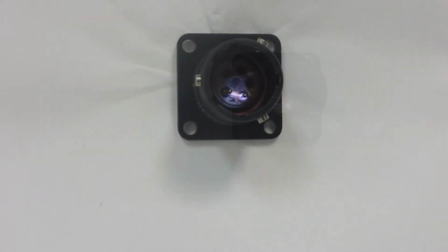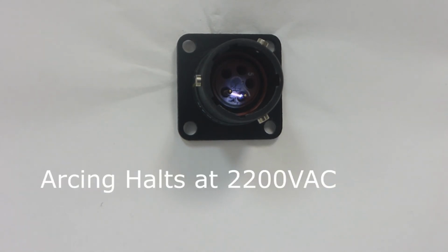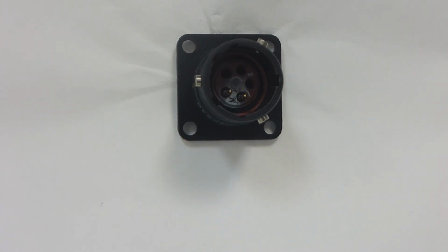Now we adjust the camera here, and we're starting to ramp down the voltage. At this point we're slowly lowering it down, and you can see and hear the buzzing stop. The arcing actually halts at 2200 volts AC.